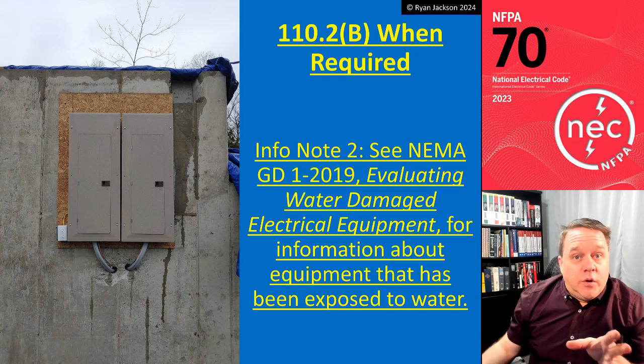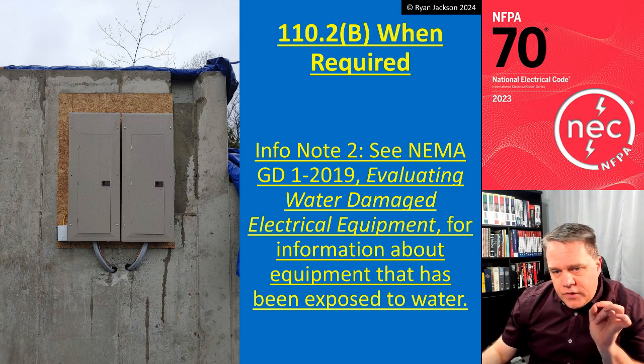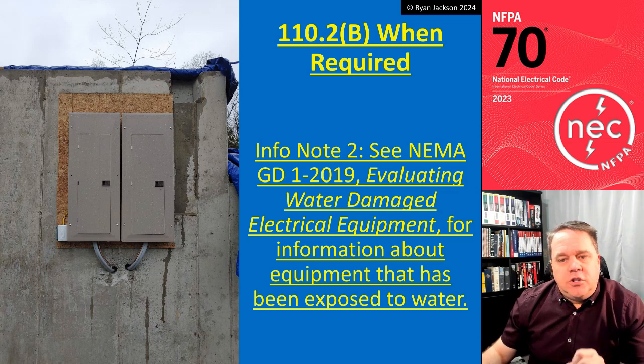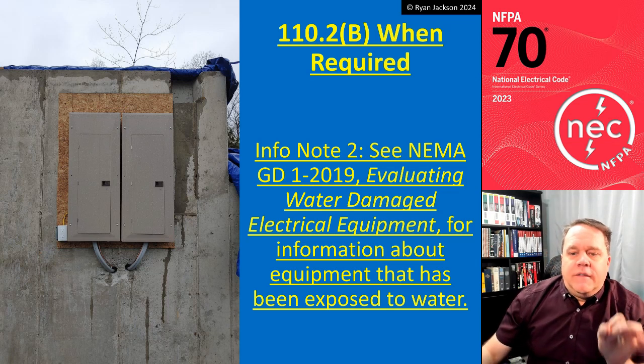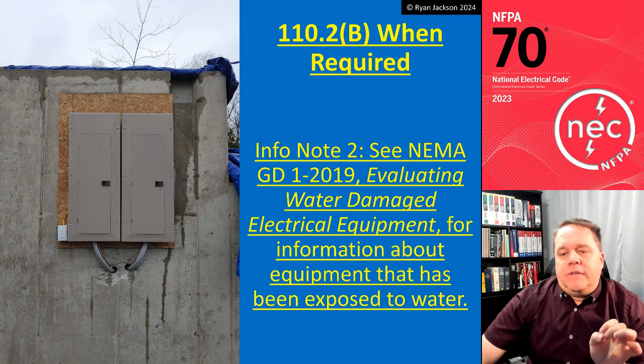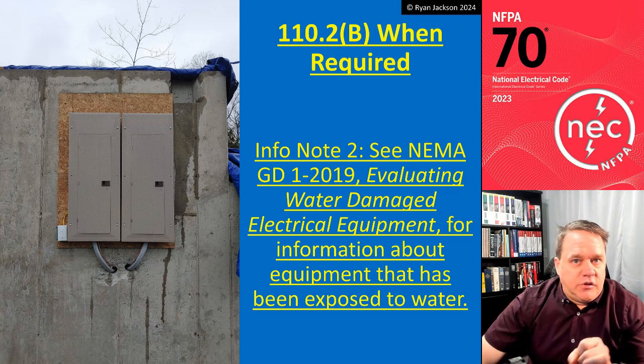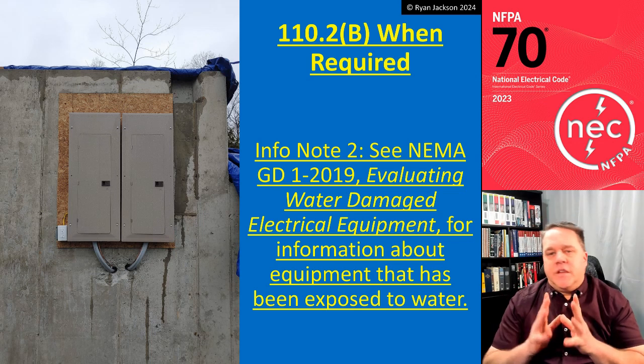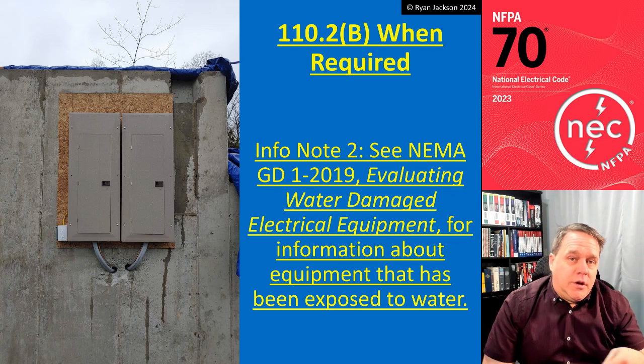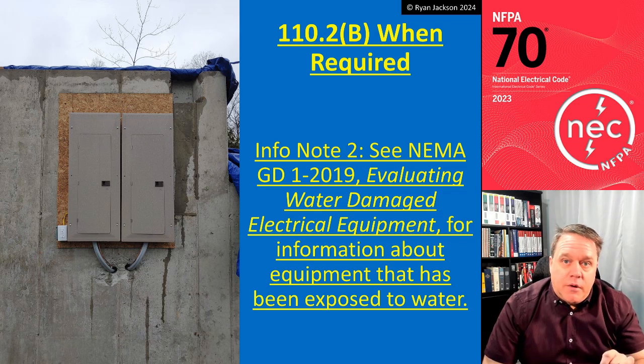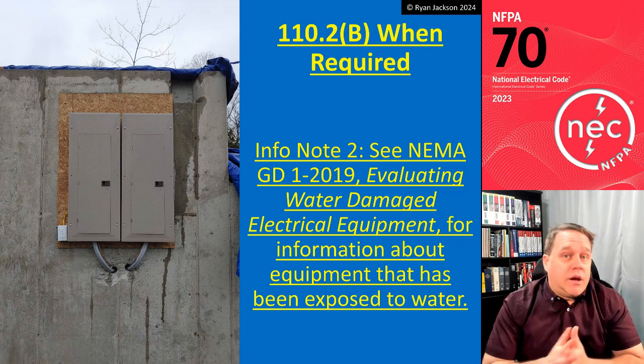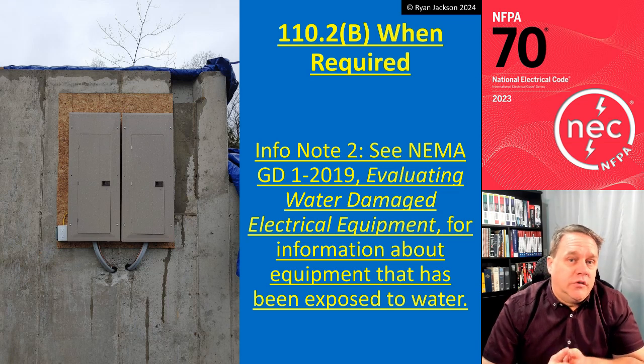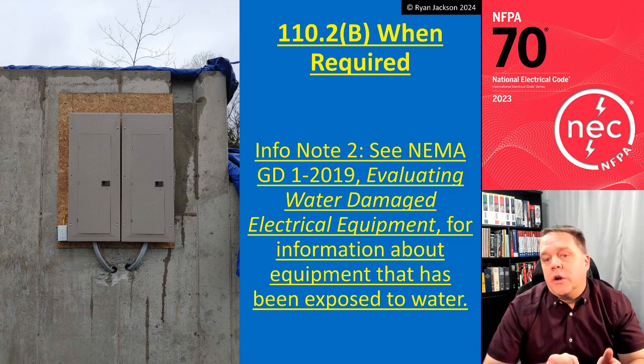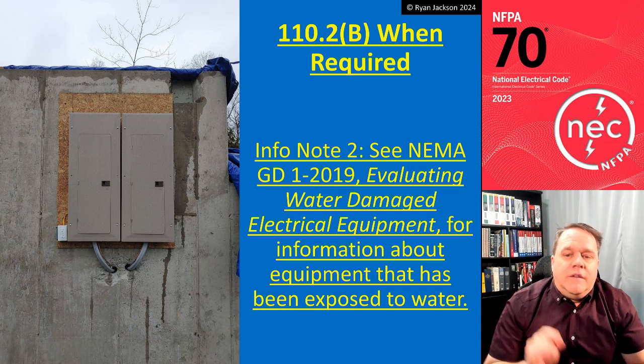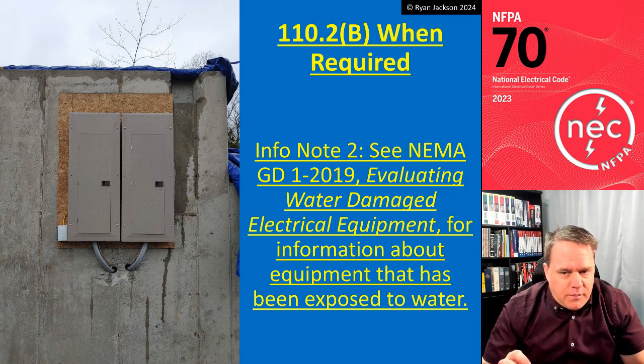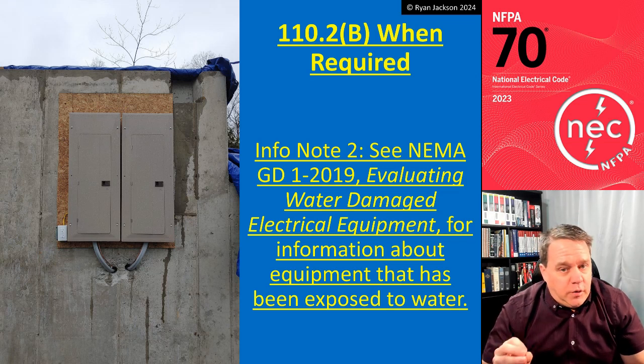There's another informational note here that we added for the 2024 that tells us to take a peek at NEMA GD1-2019, Evaluating Water-Damaged Electrical Equipment, for information about equipment that has been exposed to water. All right. This is a free download from NEMA. If you go to NEMA.org, you'll need to create a username and password, but it's free. And I recommend doing it. NEMA has a lot of good resources out there that are free. So go to NEMA.org, get yourself this document, Evaluating Water-Damaged Electrical Equipment, for evaluating equipment that's been exposed to water.